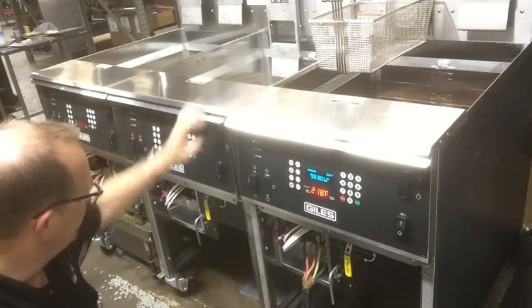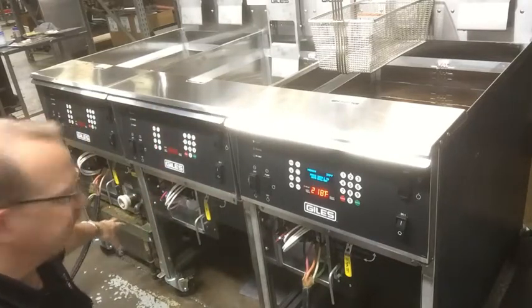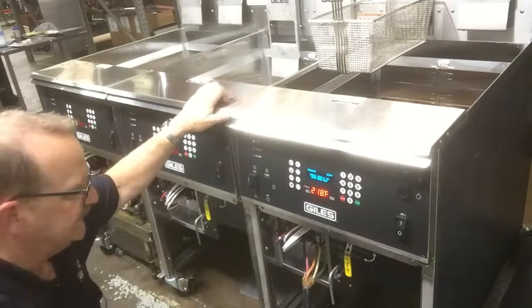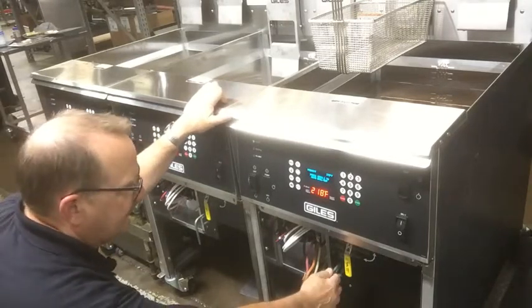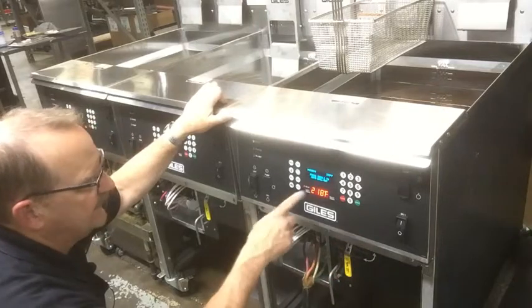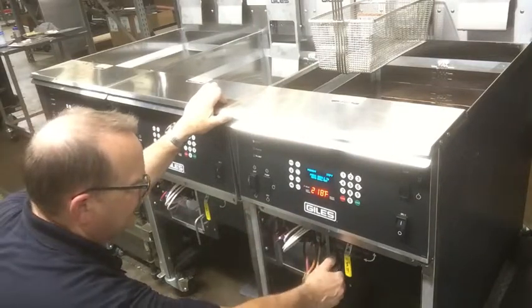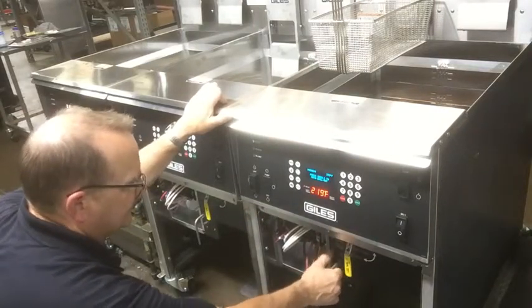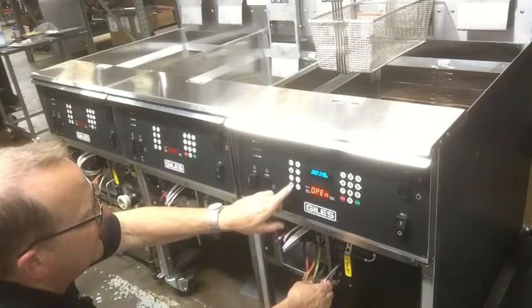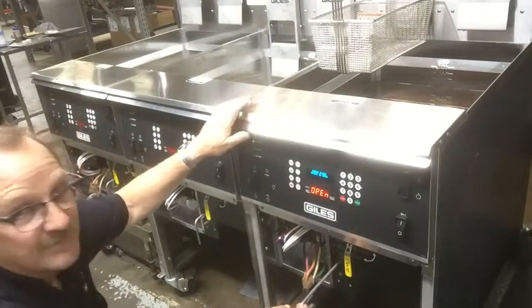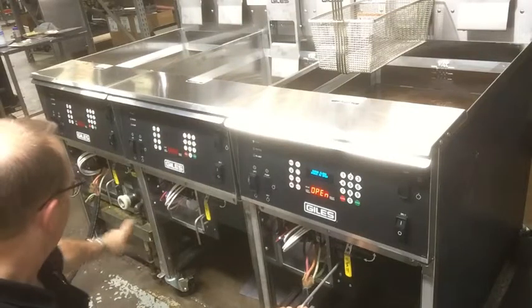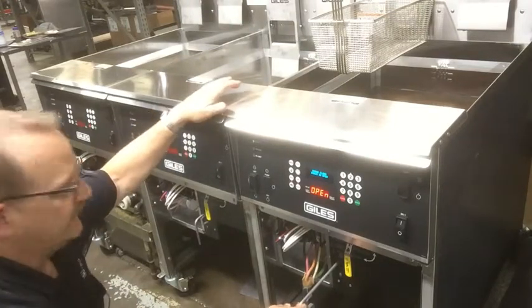Now the first thing we want to do is make sure that there's nothing in the filter pan. We've just cleaned that and connected it. So we're going to open up this drain valve. Now when I lift this up and open it, it will alarm and tell me that the drain is open. So I'm up. There it goes, open. I can silence that so that I don't have to hear it. So right now the oil is draining into the filter pan.